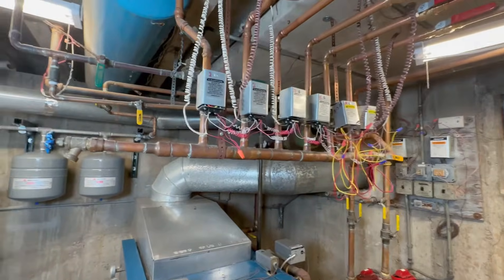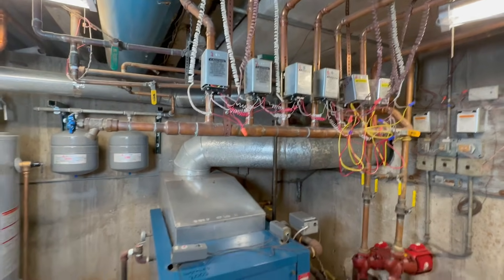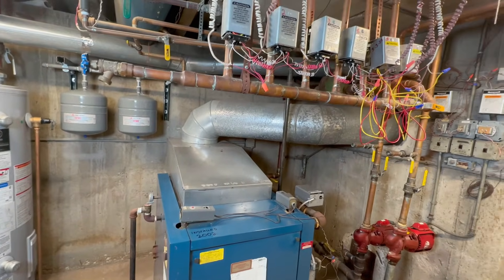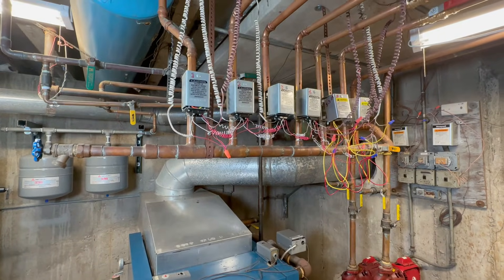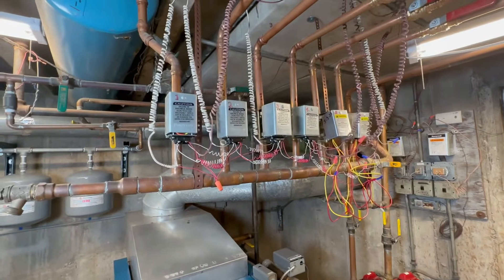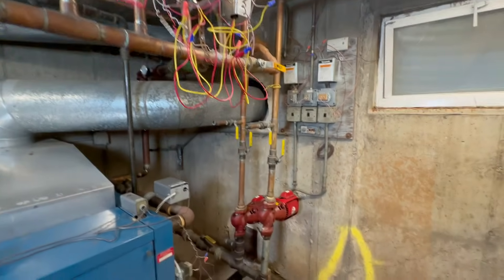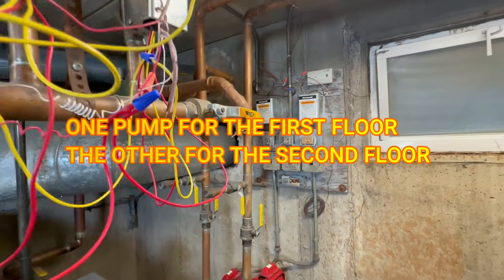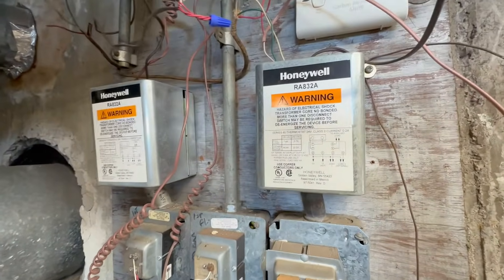This is not a no-heat call, this is a too-much-heat service call. This is a 400,000 BTU boiler that controls 12 apartments — six on the first floor and six on the second floor. These are the zone valves for the first floor, and we have two pumps, one for each floor. What controls the pump is the Honeywell relay RA832A.